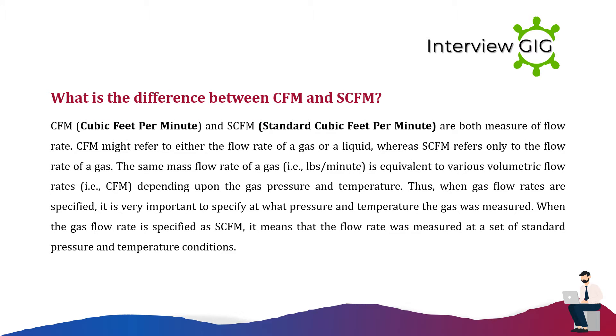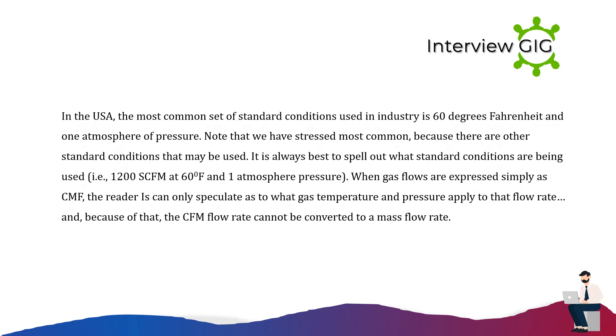What is the difference between CFM and SCFM? CFM (cubic feet per minute) and SCFM (standard cubic feet per minute) are both measures of flow rate. CFM may refer to either the flow rate of a gas or a liquid, whereas SCFM refers only to the flow rate of a gas. The same mass flow rate of a gas (pounds per minute) is equivalent to various volumetric flow rates (CFM) depending on gas pressure and temperature. When gas flow rate is specified as SCFM, it means the flow was measured at standard pressure and temperature conditions — in the USA most commonly 60°F and one atmosphere. It is always best to specify the standard conditions being used, e.g., 1200 SCFM at 60°F and one atmosphere. When flows are expressed simply as CFM, the reader can only speculate about temperature and pressure, so the flow rate cannot be converted to a mass flow rate.